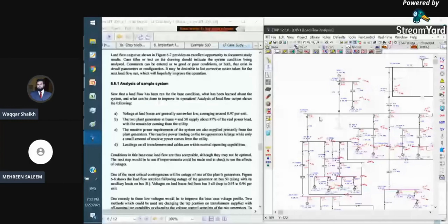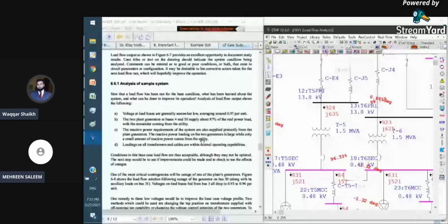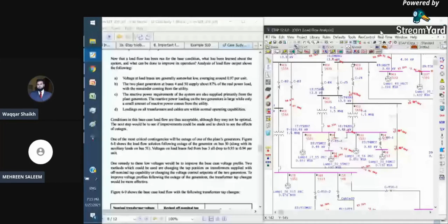Now the standard says that one of the most critical contingencies will be the outage of one of the plant's generators. So let us make a problem here. In this normal running scenario, everything is fine. But what happens if one of the generators goes out of service? Let us do this exercise. I will open this breaker, and now I will run the simulation.